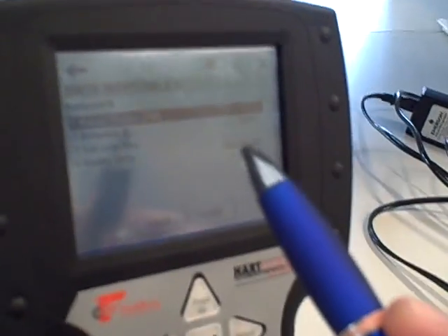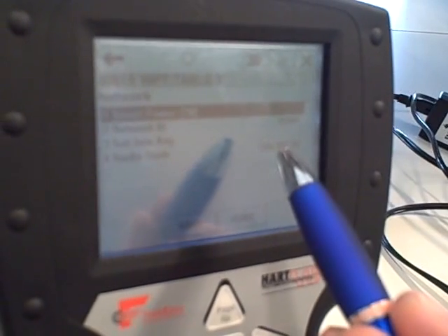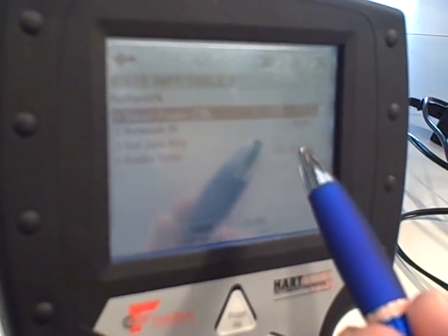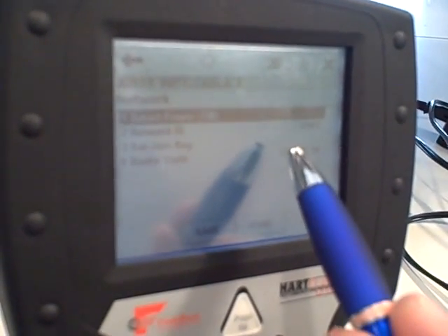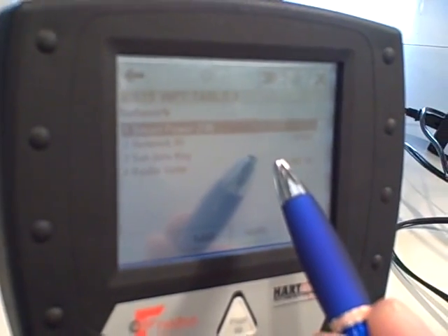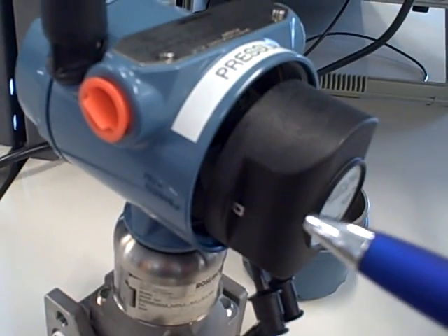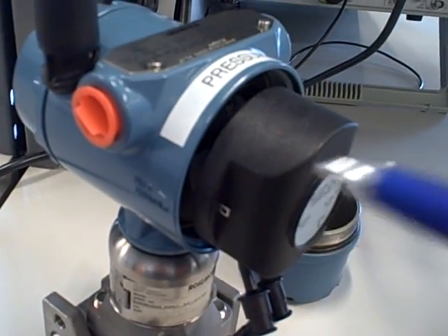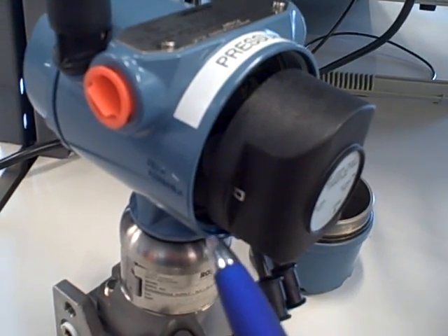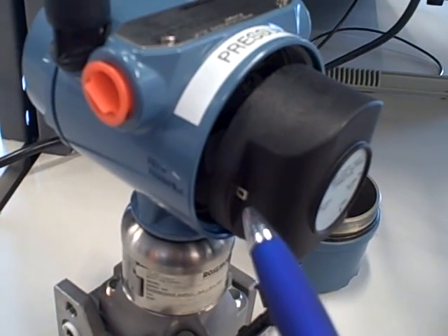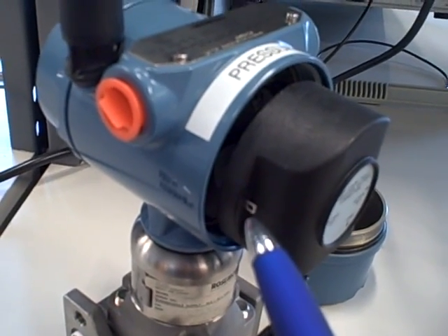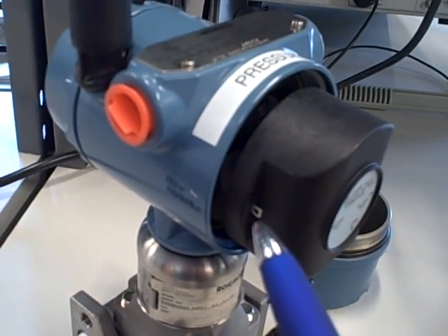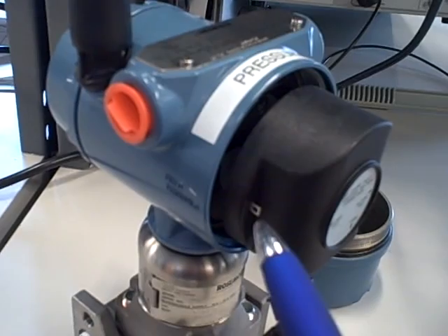Someone has to physically connect a HART communicator to the device and set the network identification number and the join key, which is like a password. Unless those parameters are set properly, matching the wireless gateway device, there's no way this particular transmitter can talk to that gateway. So security is handled on a physical basis by someone coming up to this transmitter and programming it with the appropriate Network Identification Number and join key. Again, the join key can be thought of as a password.